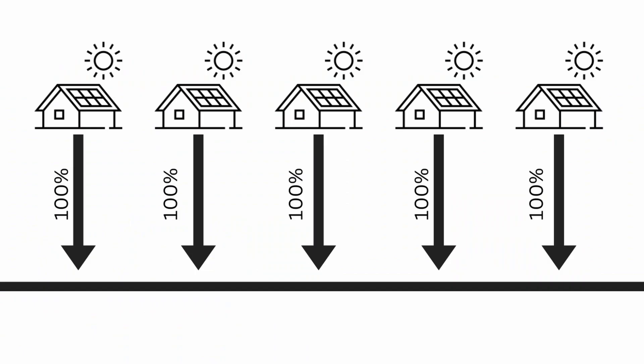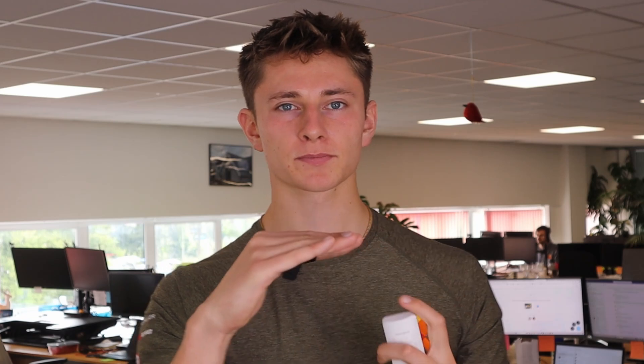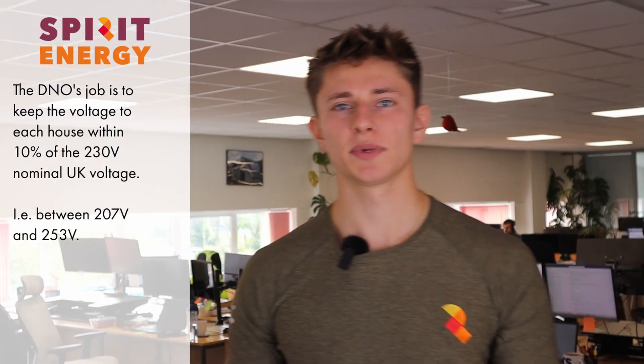The DNO will look at the most impactful scenario, which is when all systems in the local area are exporting at full capacity to the grid. This is why on sunny days you do sometimes get problems with inverters shutting down due to high voltage. However, this issue is quite rare nowadays, as most inverters can operate up to 262 volts, whereas the grid can only go up to 253 volts.